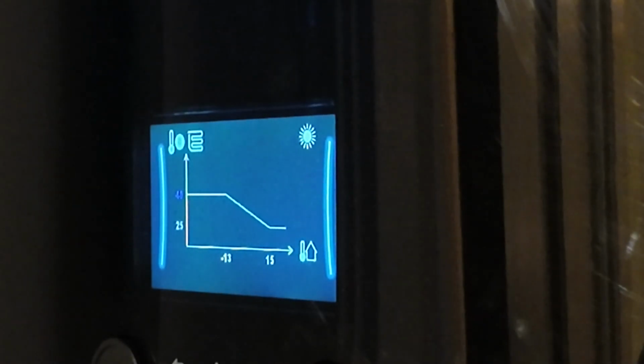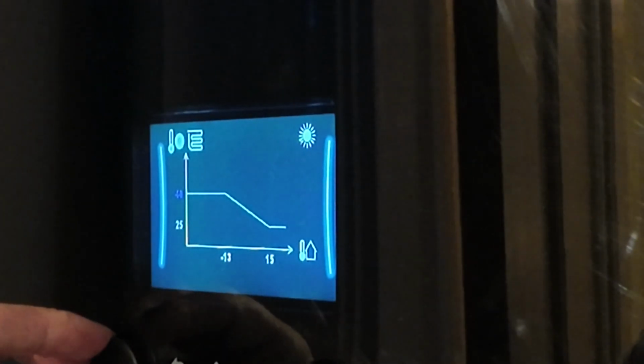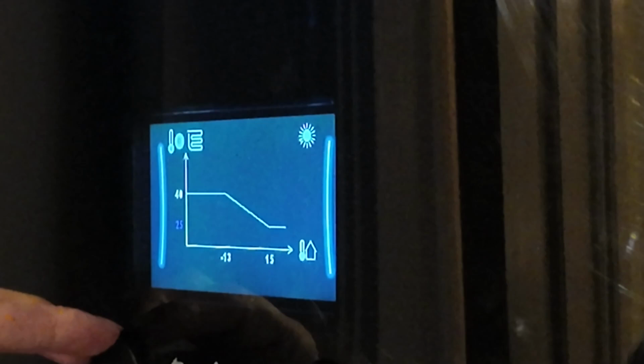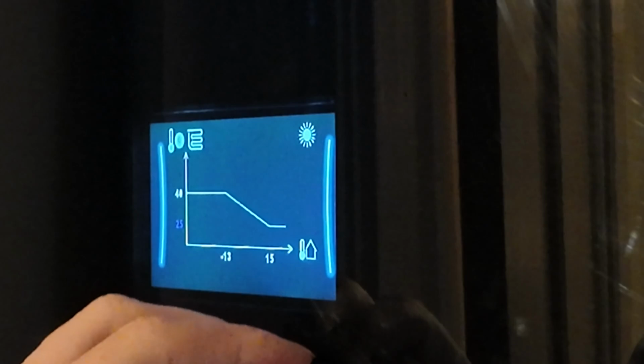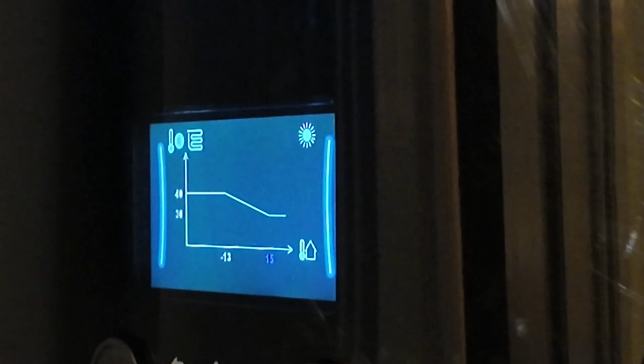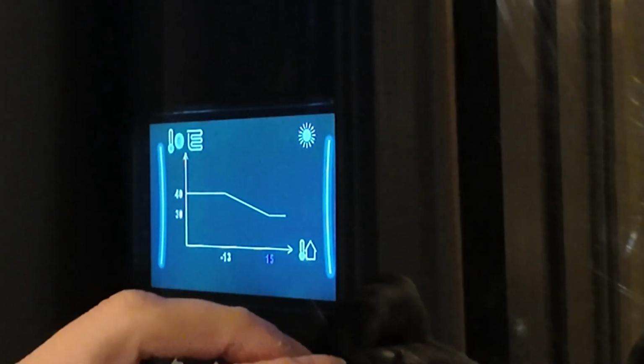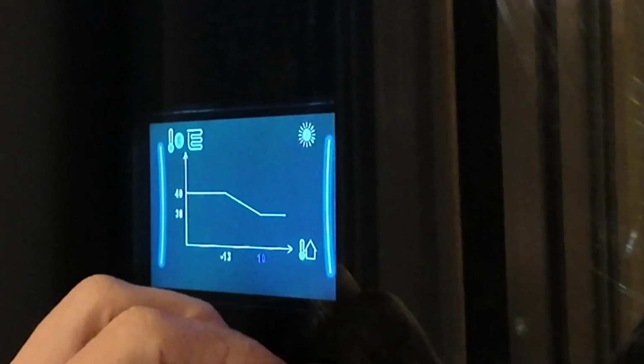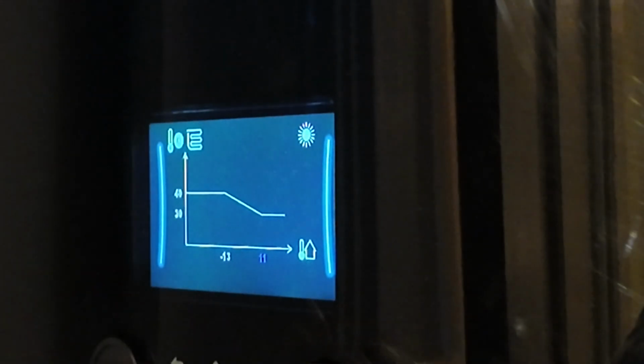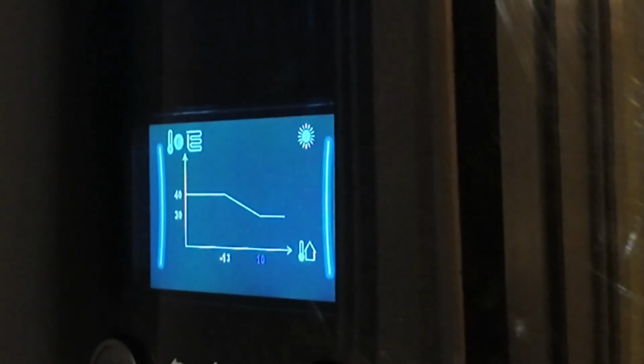Now, one of the things you can see is that we've got a set point minimum flow temperature of 25 degrees Celsius. And realistically, I want to bring that up to 30 degrees. But the problem I've got is that I want to reduce the temperature down here to 5 degrees. Unfortunately, you can't. You can only go as far as 10 degrees here, and you can't go any further than that. And that means I have to have two different modes of operation, and I have to manually change between the two. So I'm just going to discard these changes here.